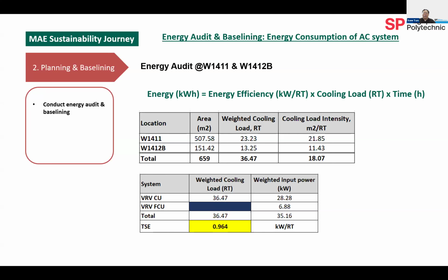Based on the audit finding of the air conditioning system, we carry out a more detailed analysis to pinpoint the specific areas where energy performance could be improved. We observed that energy efficiency was relatively acceptable for this finding. The energy efficiency of the equipment is 0.964 kilowatt per RT. However, the cooling load intensity, as shown in this table, was particularly high at 18.07 meters squared per RT.